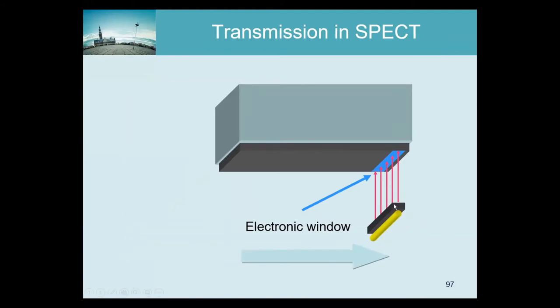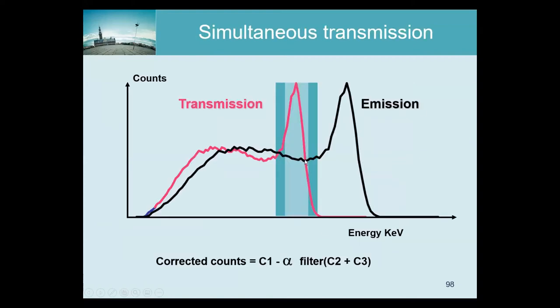You can also tell the computer exactly where to expect transmission photons, and just before and after the source passes a particular position, what you measure should be emission only — giving you a good estimate of the emission contribution in your transmission window. Then the triple energy window method is applied, because you have scatter from the transmission source as well as from the emission activity. You put two windows assuming they measure just the scatter contributions, add them, filter them, find a good weight, and subtract them to get the transmission counts.